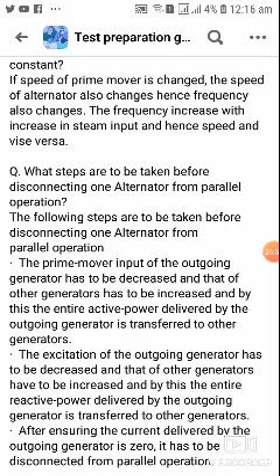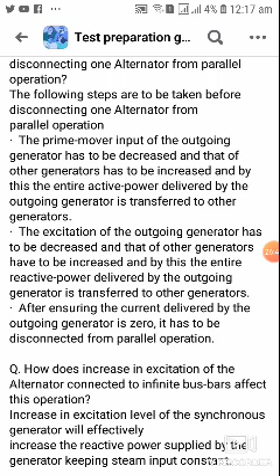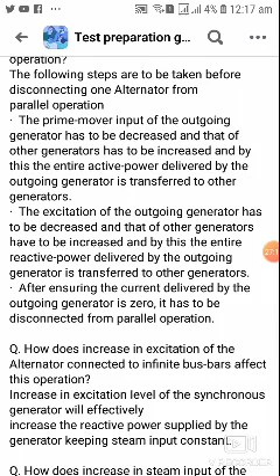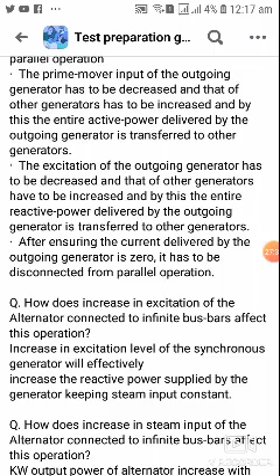Question number 49. What steps are to be taken before disconnecting one alternator from parallel operation? The following steps are to be taken before disconnecting one alternator from parallel operation. The prime mover input of the outgoing generator has to be decreased and that of the other generator has to be increased. By this, the entire active power delivered by the outgoing generator is transferred to the other generators. The excitation of the outgoing generator has to be decreased and that of the other generators has to be increased, and by this the entire reactive power delivered by the outgoing generator is transferred to the other generators. After ensuring the current delivered by the outgoing generator is zero, it has to be disconnected from the parallel operation.